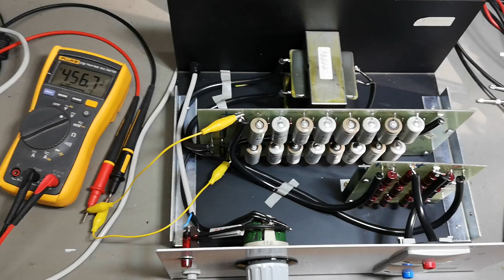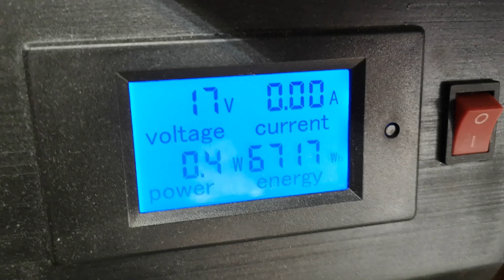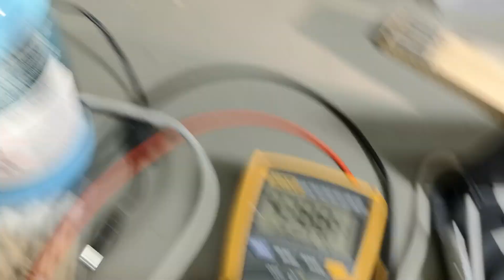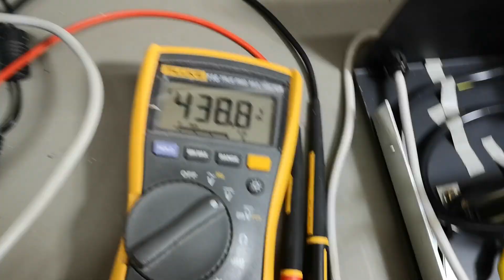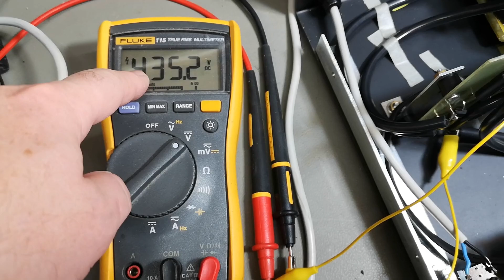We got 442, it varies a little bit, but it's just before I had 450. So this is my DC voltage, and look at that, 17 AC input. So that means 17 divided up to what we have, 230 volts, so that is 13.5 times, multiplied by 450, so that is a little bit more than 6,000 volts this thing can potentially create. So that means the scale on the front panel is not lying.